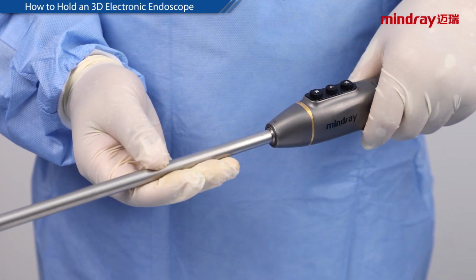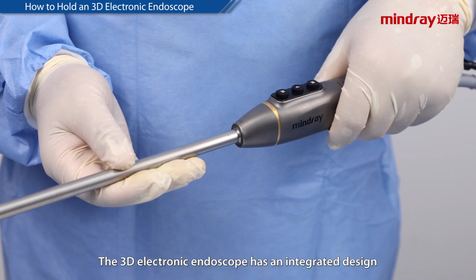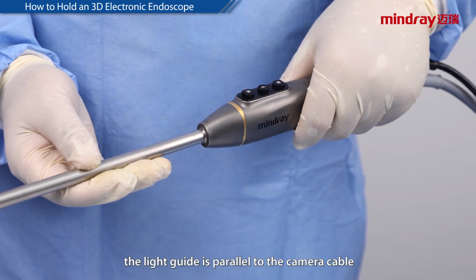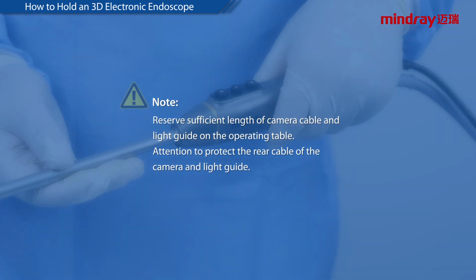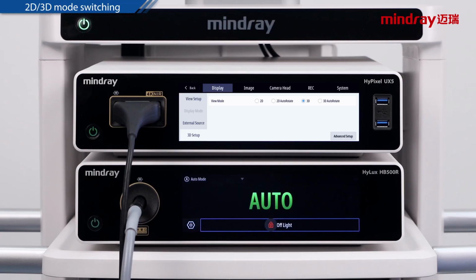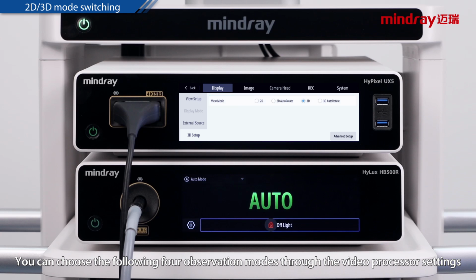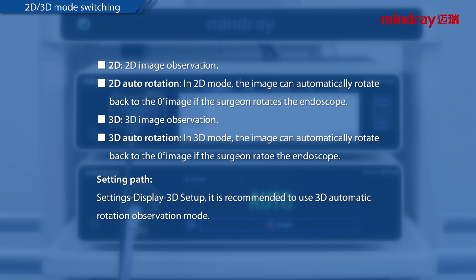How to hold a 3D electronic endoscope. The 3D electronic endoscope has an integrated design. The light guide is parallel to the camera cable so it can be held with one hand. Note: reserve sufficient length of camera cable and light guide on the operating table. Attention to protect the rear cable of the camera and light guide. 2D 3D mode switching. You can choose the following 4 observation modes through the video processor settings: 2D, 2D image observation, 2D auto rotation. In 2D mode, the image can automatically rotate back to the 0-degree image if the surgeon rotates the endoscope. 3D, 3D image observation, 3D auto rotation. In 3D mode, the image can automatically rotate back to the 0-degree image if the surgeon rotates the endoscope.